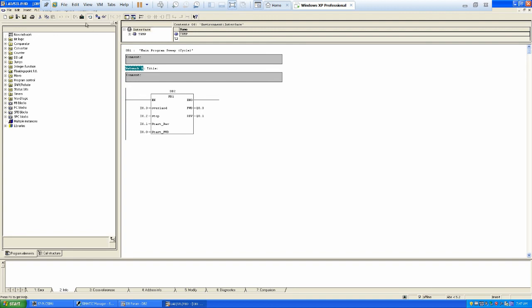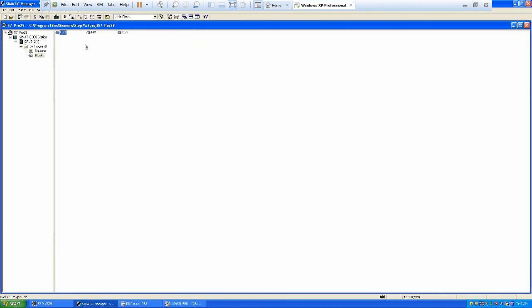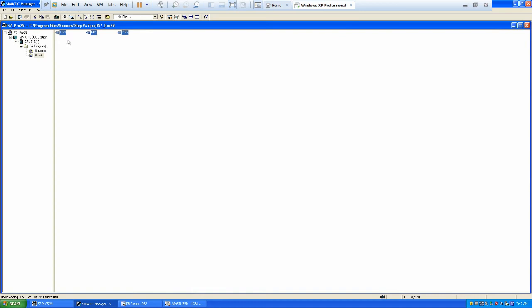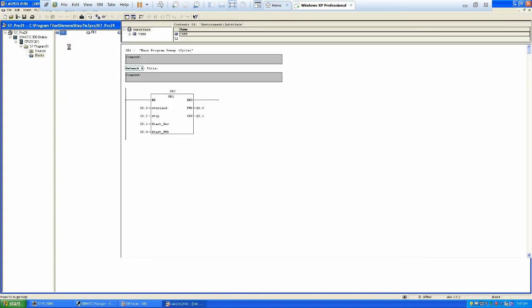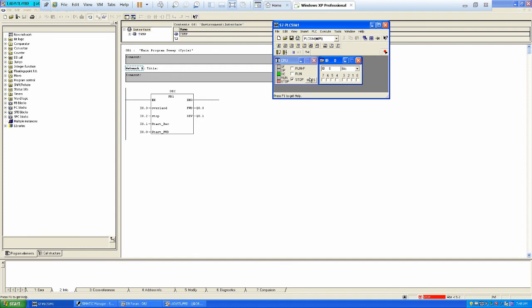This program is almost ready for testing. We will just download it. When you are downloading the program, you have to download all three items, select all three, and then yes — so you have downloaded the program. Now you can open up the operator panel. Make sure our overload and stop button inputs are here and should always be one, because these are in normally closed condition in the field.